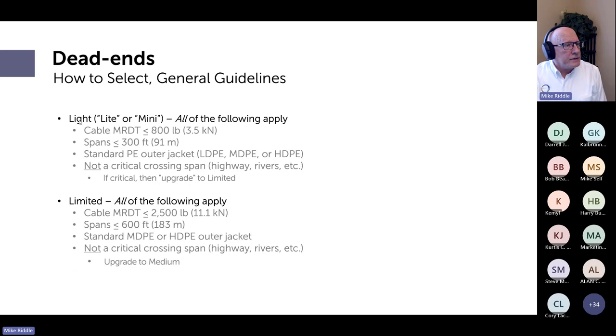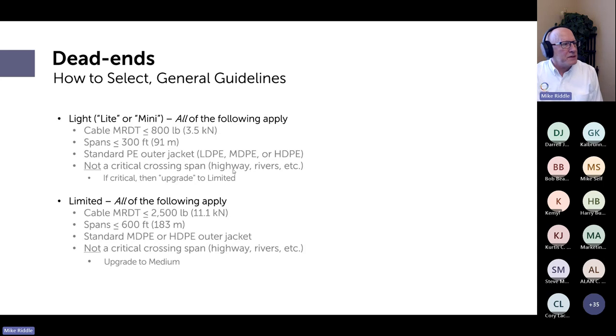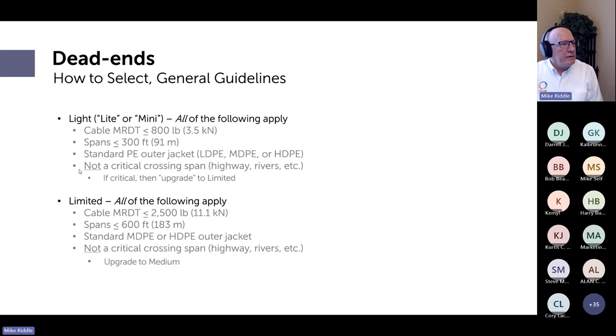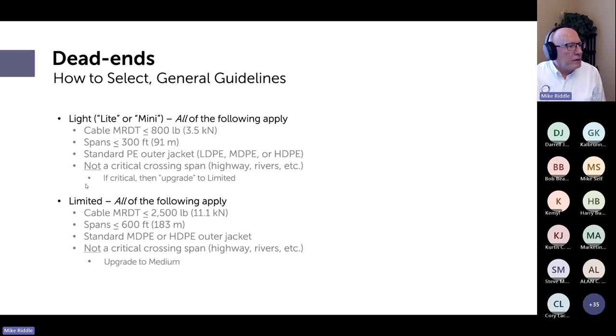Light dead ends can be used if all of the following apply: cable MRDT or MRCL less than 800 pounds (3.5 kN), spans less than 300 feet, a standard polyethylene outer jacket (LDPE, MDPE, or HDPE are all acceptable), and the span is not a critical span. If it crosses a highway, river, or other important feature, upgrade to the next class — limited.